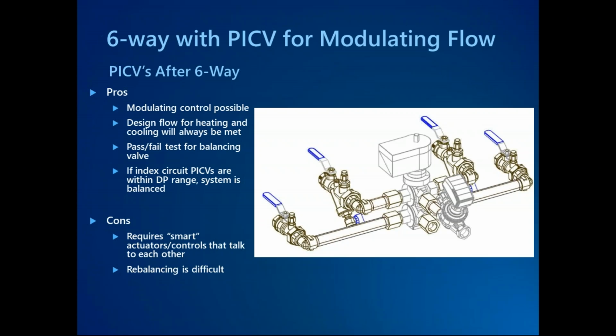The PICV actuator needs to know if hot water or cold water is flowing through it, because a lot of times those are going to be different max GPMs. So if you have 8 GPM on your cooling side and 2 GPM on your heating, the PICV needs to know what its current, quote unquote, max GPM is for the application. And if that difference between GPMs is very drastic, then you're going to have very poor control on the lower flow, because if the PICV is designed to handle that 8 GPM solution, but also has to be able to modulate down to that 0 to 2 GPM solution for heating, the amount of modulation is going to be very, very limited.